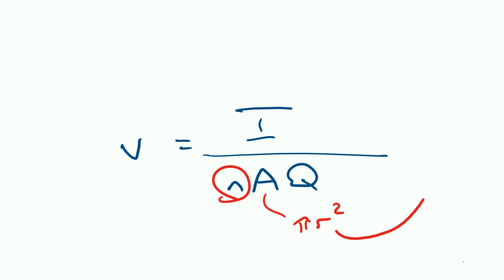We call them gauge. A standard wire gauge 19 is about 1 millimeter thick. It's actually slightly over, like 1.016 millimeters off the top of my head, but let's just call it 1 millimeter. It's very close to that, which means that our r is actually going to be only half of a millimeter, right? Because it's the radius, not the diameter.